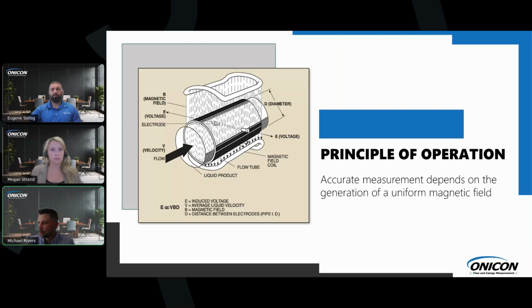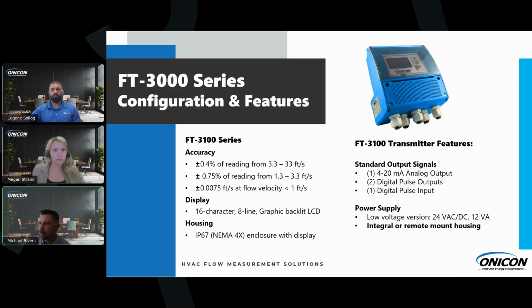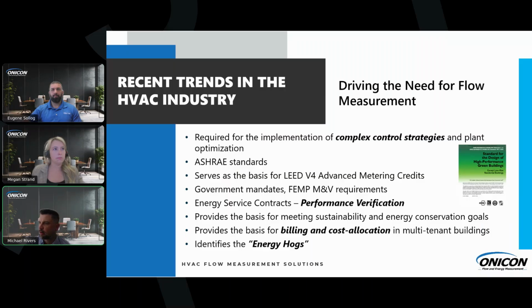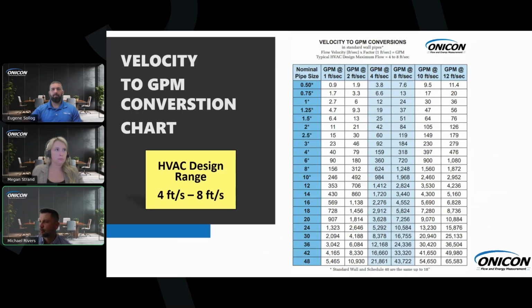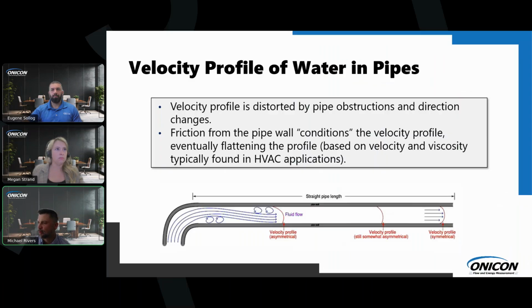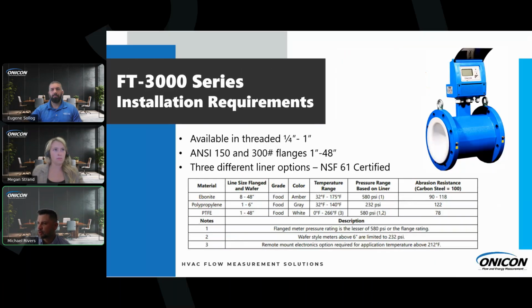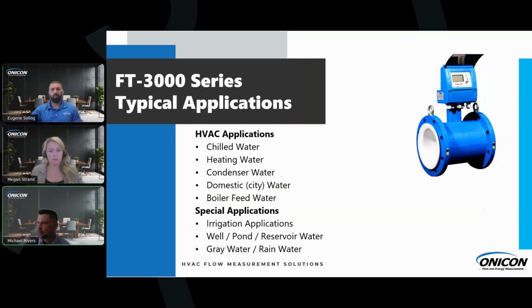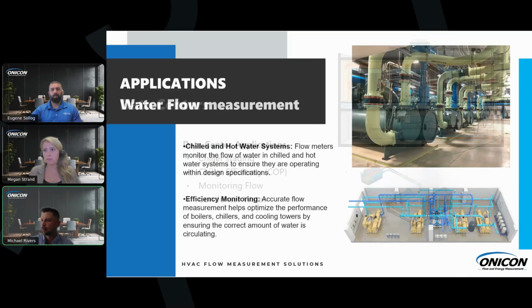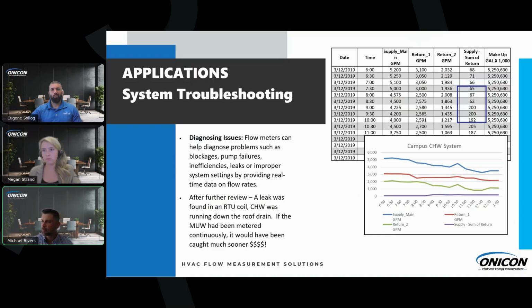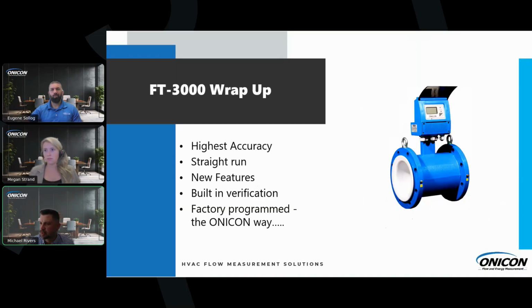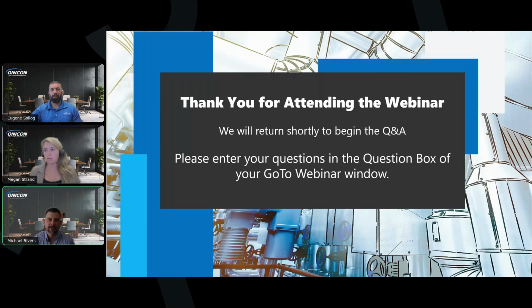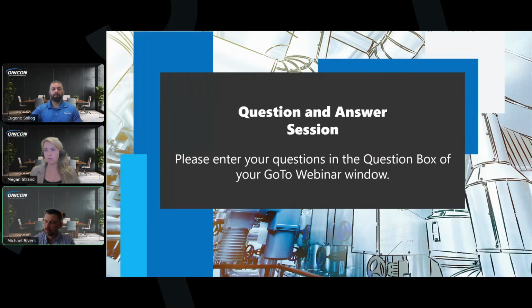So two good questions from Vince from Precise Engineering. The first is around, some owners like to have a bypass installed around their flow meters for any maintenance required. However, with no moving parts, it's hard to imagine what kind of maintenance would be required for an inline mag meter. Do you recommend installing a bypass around these flow meters, and if so, what specific instances and applications? Yeah, this is a great question, and it's probably not a super clear answer, so I'll take this one.